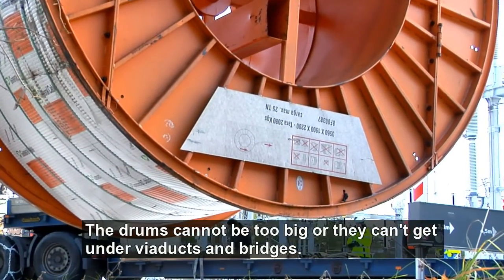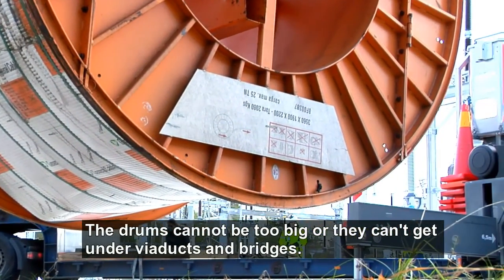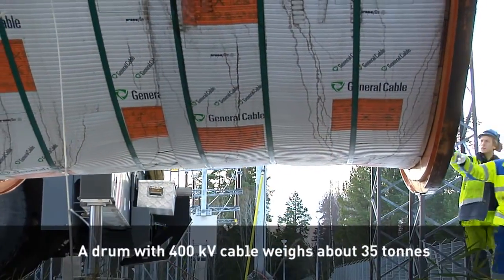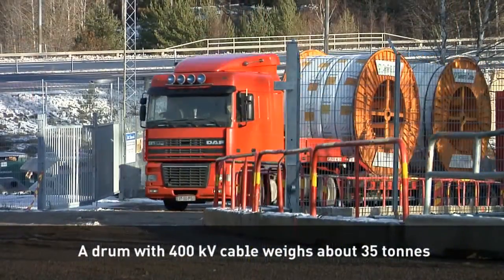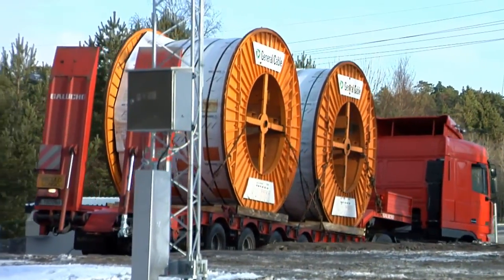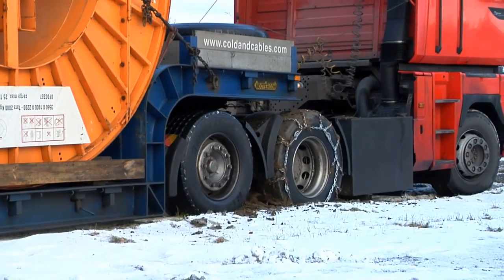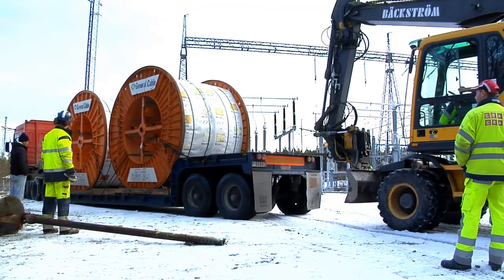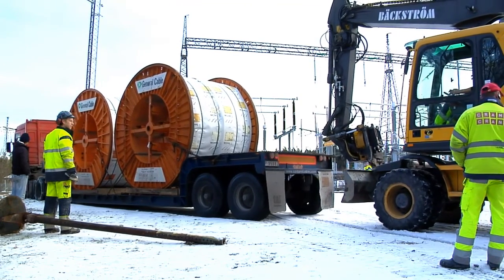The drums must not be too large for transport, or they can't get under viaducts and bridges. The working area is usually the length of two cable drums, approximately 1,800 meters. The drums are moved to the cable trench and the cables are extended, one drum in each direction.